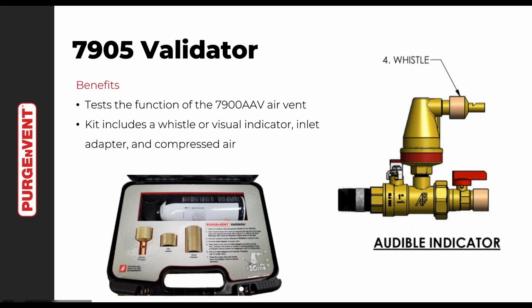We offer a product we call the Validator, and this device actually gives you a methodology to push air backwards through our product to test that our air vent is working properly, and will help you be in compliance with the NFPA 25-2023 requirement for making sure your air vents are working properly.